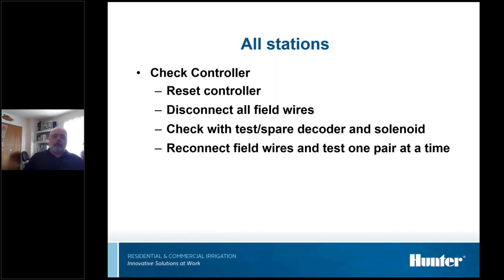And then, once we prove the controller works, we hooked our spare decoder up and it turned on, we're going to start reconnecting wire paths one at a time. And we're trying to find the wire path that causes the problem. Just by doing this, sometimes you can get most of the system working by doing nothing other than just disconnecting that wire. Not perfect, but half of the system operating is a lot better than none.